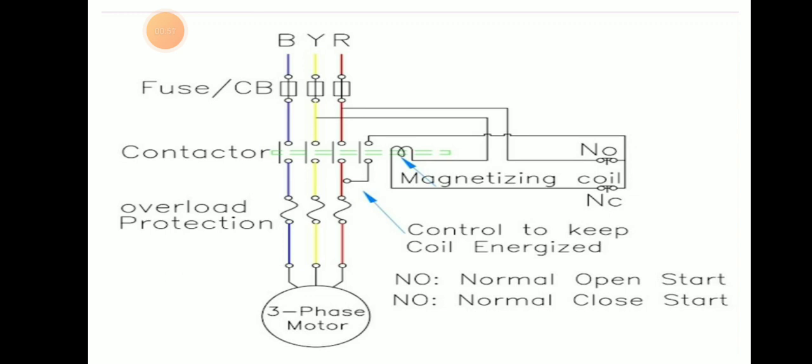There is a NO (normally open) contact for the magnetizing coil and NC (normally closed) contact for stopping. NO is normally open at start and closes during running. Overload protection is also provided. After the contactor, it goes to the three-phase motor, and there is a control circuit to keep the coil energized from the magnetizing coil.